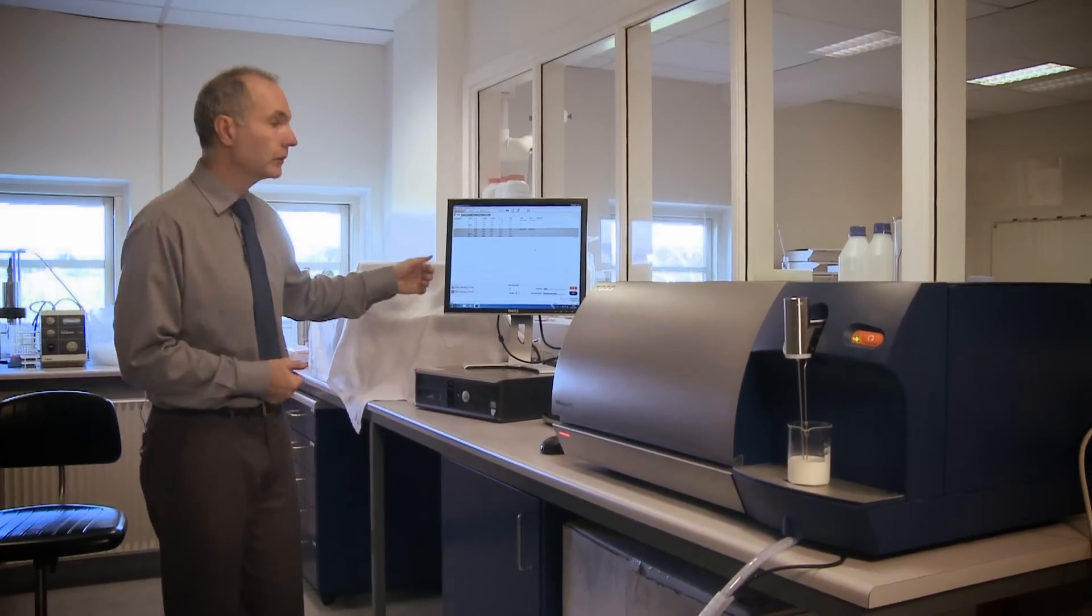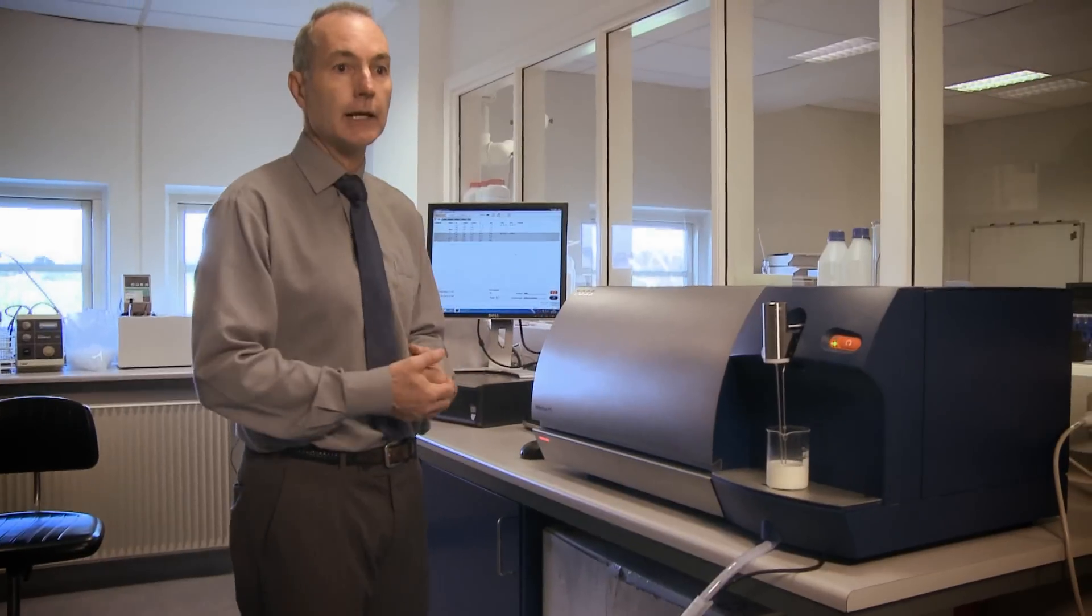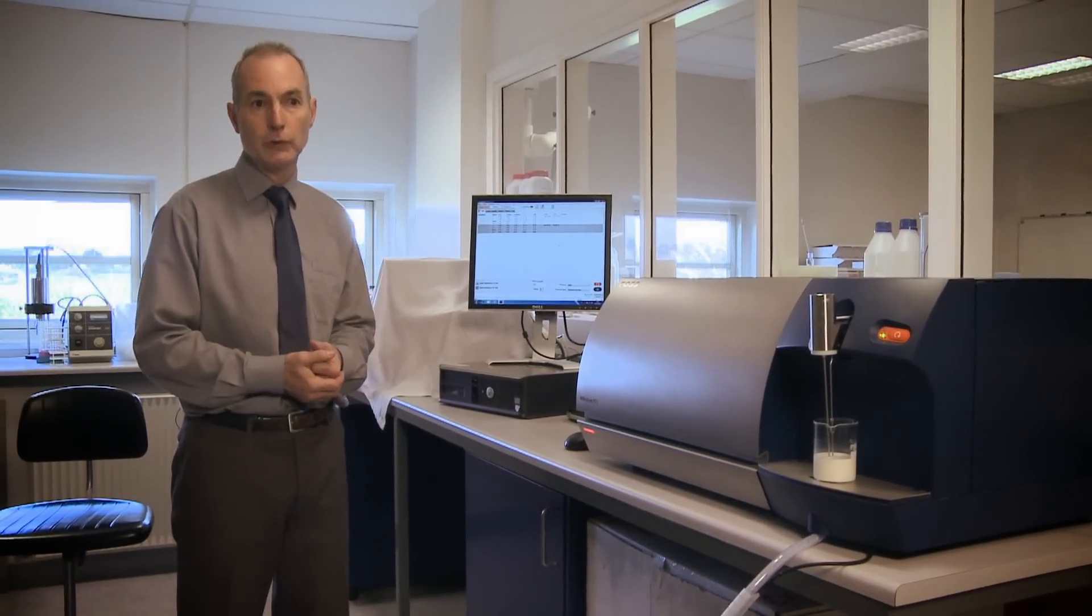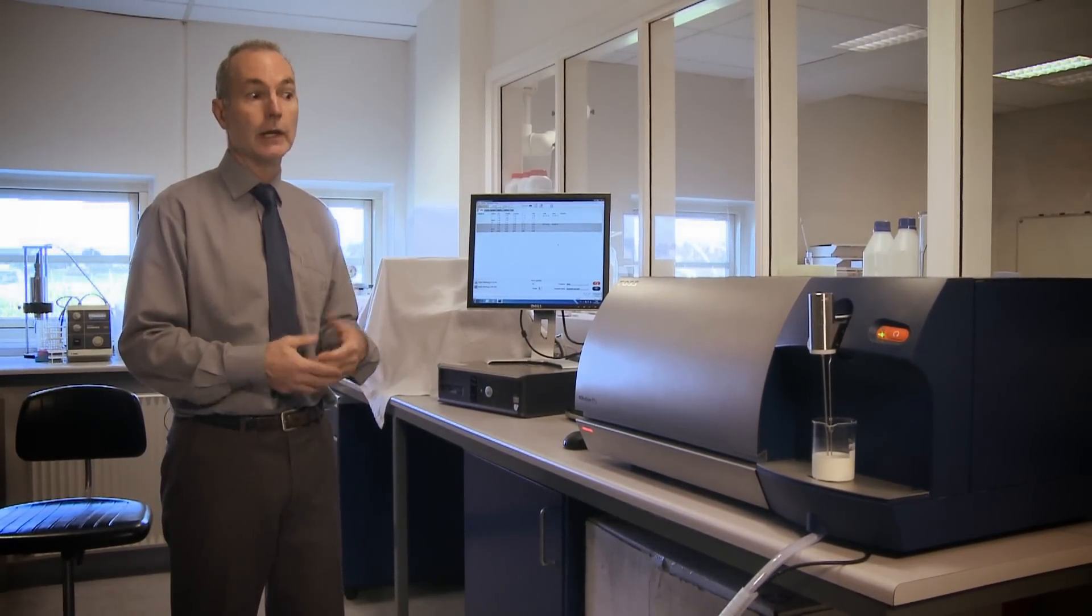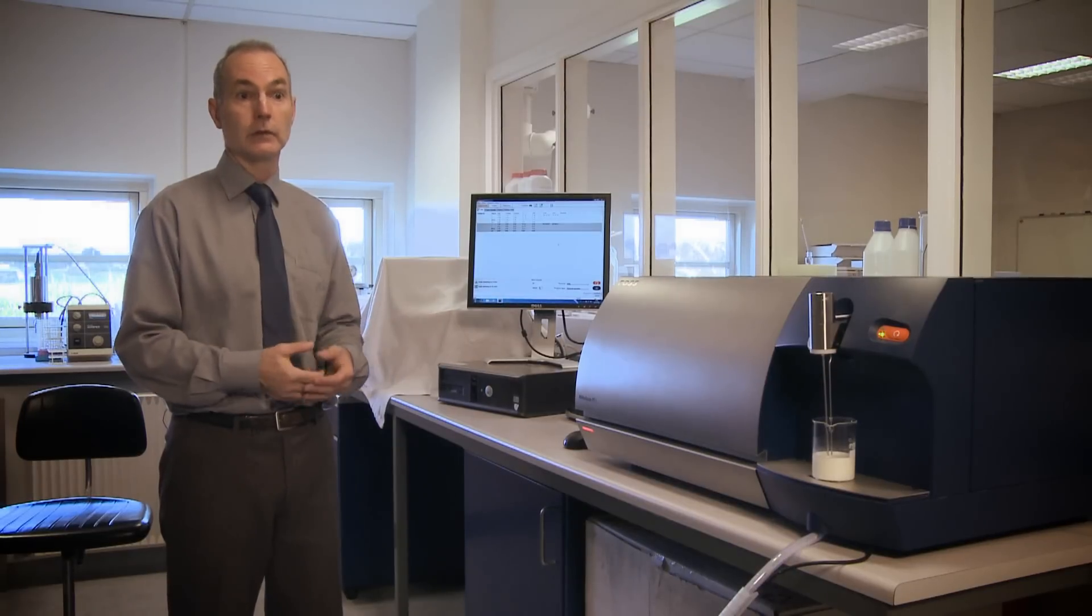With the calibration supplied on the instrument, we have multi-components, meaning we can have fat, protein, lactose, total solids. And all of that can be just analyzed in 30 seconds. So we do have a true multi-component dairy products analyzer. And the main thing there is it is extremely rapid.